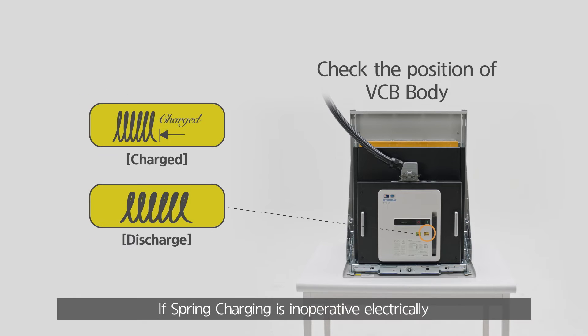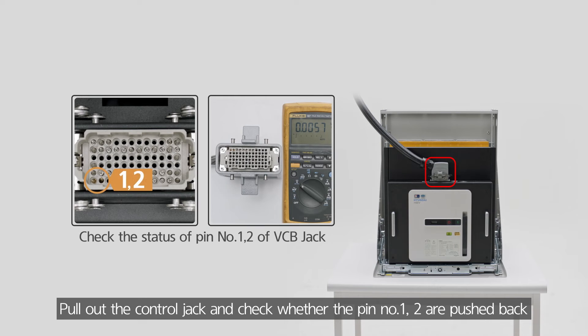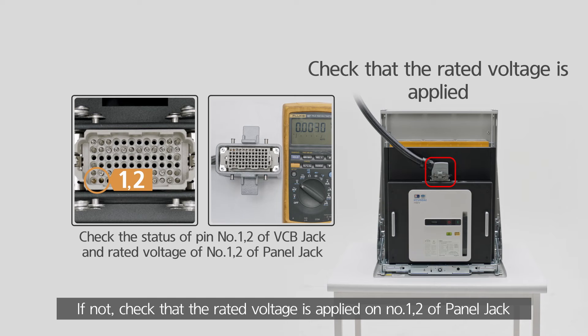If spring charging is inoperative electrically, pull out the control jack and check whether pin number 1, 2 is pushed back. If not, check that the rated voltage is applied on number 1, 2 of the panel jack.